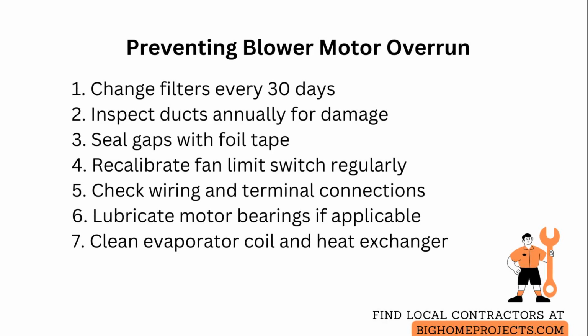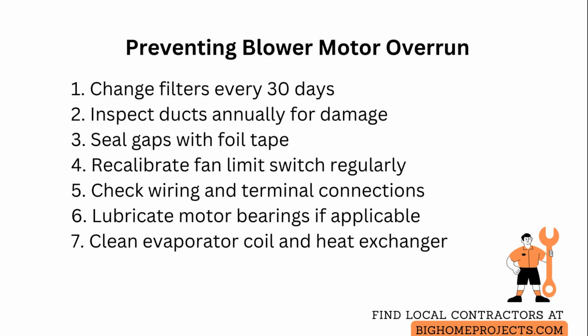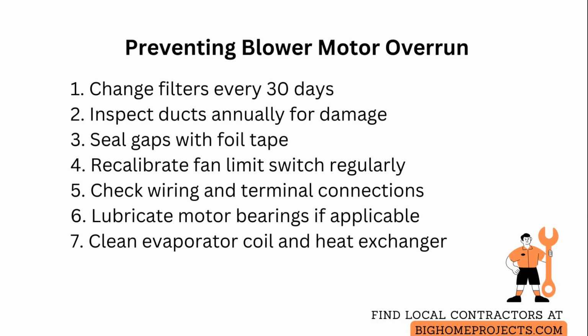Inspect supply and return ducts annually for crushed sections, disconnected joints, and heavy dust buildup. Seal obvious gaps with foil tape and remove debris to restore normal static pressure so the motor cycles properly.